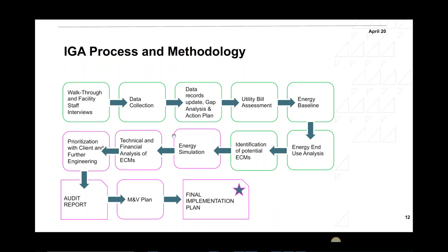Data collection: drawings, submittals, cut sheets, O&M manuals, utility data, trending from the BMS. You need to do a data records update check. Normally, we would do a checklist, send it to the client, and then get the information, and then there will be a live document to show what has been submitted yet and what is not submitted, what is available and what is not available. Then you do the utility bill assessment to see how much the building is using in terms of consumption, the EUI.